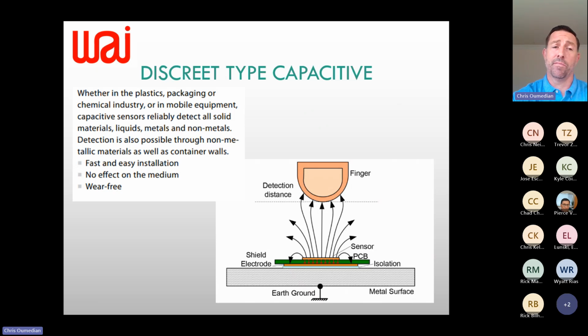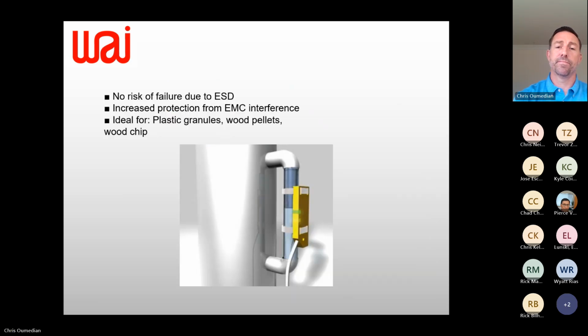Very, very immune to EMC, low cost, easy installation. You're not piercing containers. You're looking through plastic, looking through sight glass. It could be liquids, it could be solids, it could be powders, which are difficult for ultrasonics, radars, and even photoelectrics. So a problem solver for powders as well. There's a picture of our most popular, Turck's most popular capacitive sensor looking through a glass tube, sort of a sight glass that's on the exterior of a tank. And you see the little light on the bottom, it trips as that water goes above the measuring point on the sensor.